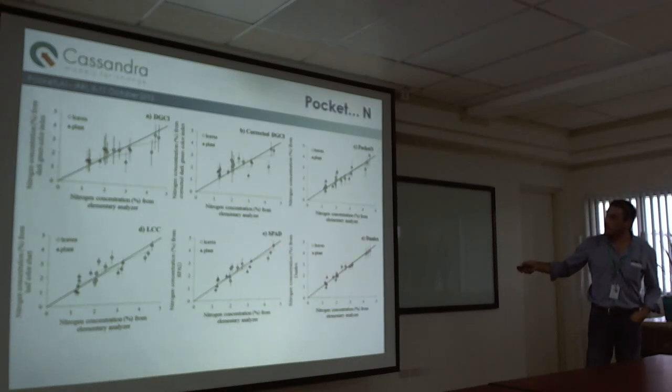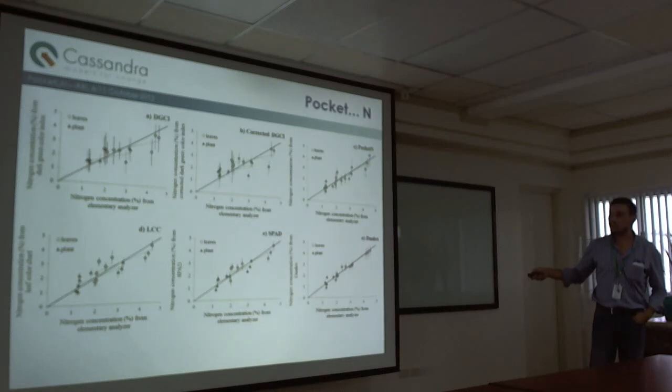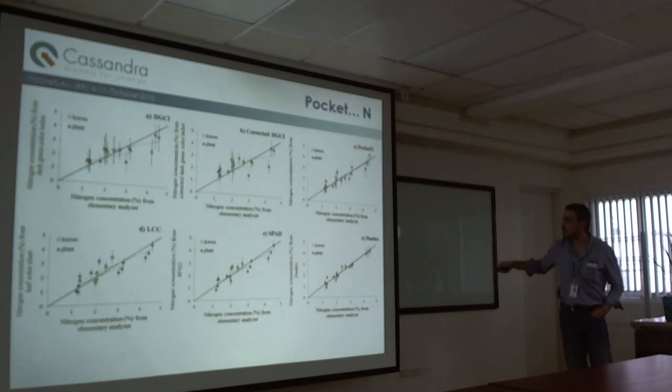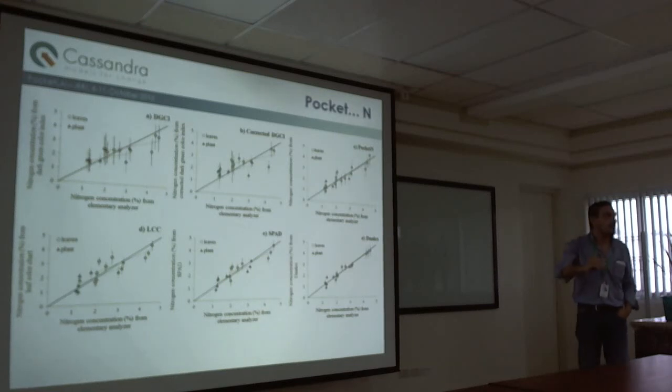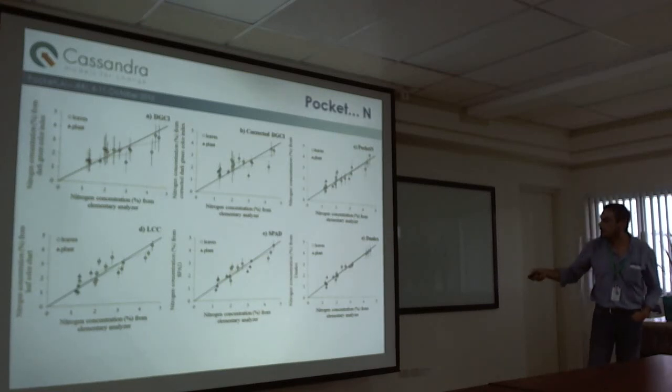Okay, let's look at what the SPAD does and look at what the Dualex does. The repeatability, you see that the variability among the mean is not so good as for the SPAD. So you need to take more measurement replicates using this Dualex. But look at the trueness.